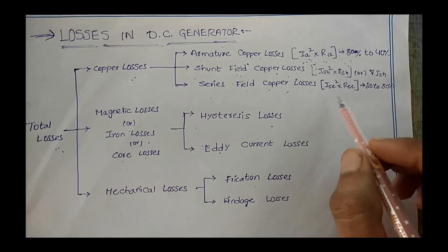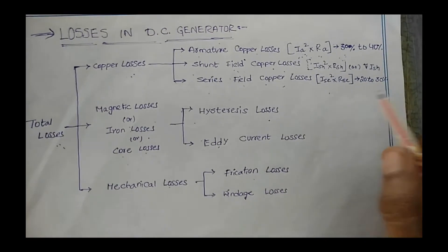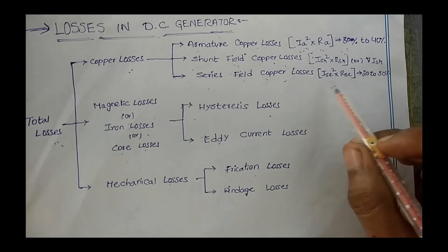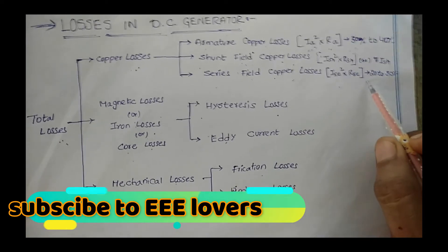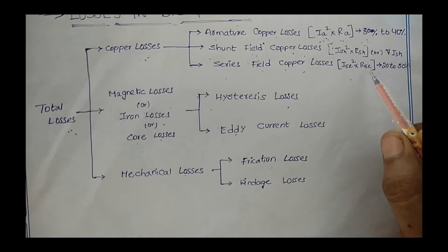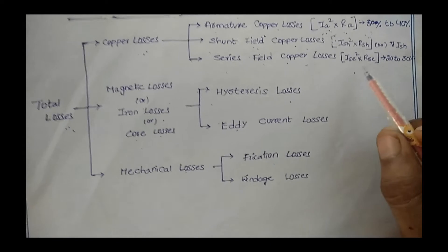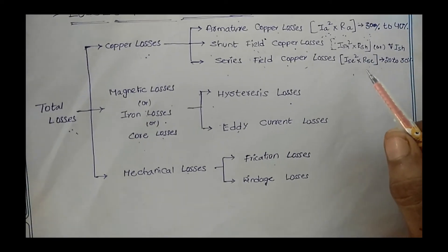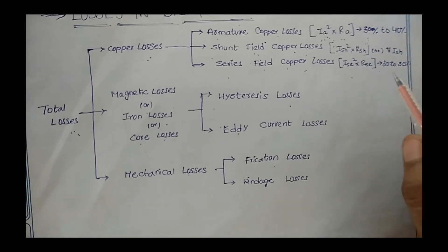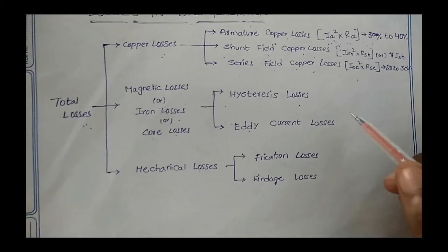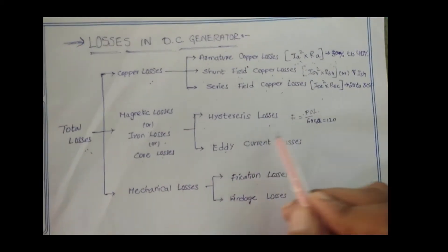Next are series field copper losses. In the case of a series generator, this loss is equal to I_se² × R_se, where R_se is the resistance of the series field winding. The field copper losses are about 20 to 30 percent of full load losses.